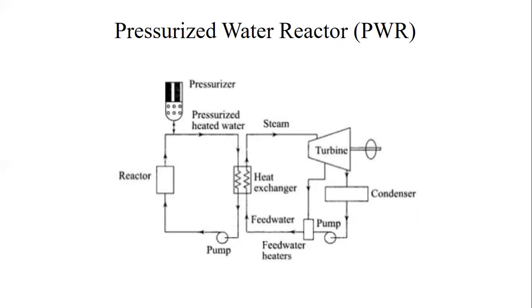In PWR, the coolant pressure must be greater than the saturation pressure at 300 degrees Celsius, or 85.93 bars, to prevent boiling. The pressure is maintained at about 155 bars so as to prevent bulk boiling. The PWR power plant is composed of two loops in series. In the schematic diagram of the pressurized water reactor, on the left hand side you can see the primary coolant loop, and on the right hand side the water-steam or working fluid loop. The coolant picks up heat in the reactor and transfers it to the working fluid in the steam generator. The steam is then used in a Rankine cycle to produce electricity.